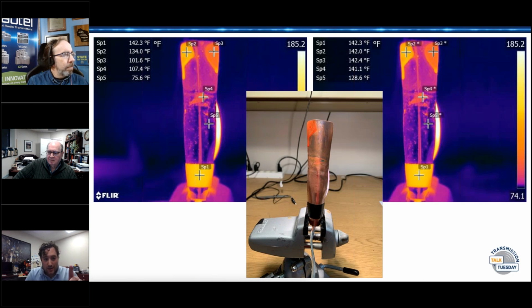Now that point, SP3, is extremely important because my camera is telling me that point is hot — hotter by 30 degrees than the supposedly coldest spot. If you look at the actual copper piece, it's invisible, it's not there, you don't see anything. So this can easily trick you and make you falsely assume something's wrong there.